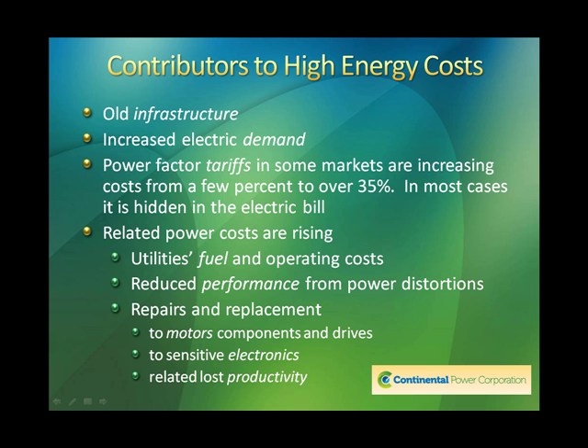Some of the contributors to high energy costs, and this is something that's good to be aware of. First of all, old infrastructure. A lot of old buildings with old wiring, old panels, old transformers. All of that contributes to higher energy costs. Secondly, increased electric demand. As more and more equipment is added into a facility, the demand goes up, sometimes exceeding the load carrying capacity of the distribution system. Thirdly, power factor tariffs in some markets are increasing costs from a few percent to over 35%. And in most cases, it's hidden in the electric bill. We find many customers that we enlighten with the fact where we show them that they are paying a penalty because their power factor is below the threshold set by the utility. This is sometimes very surprising, and it's easy to be able to reduce those costs.